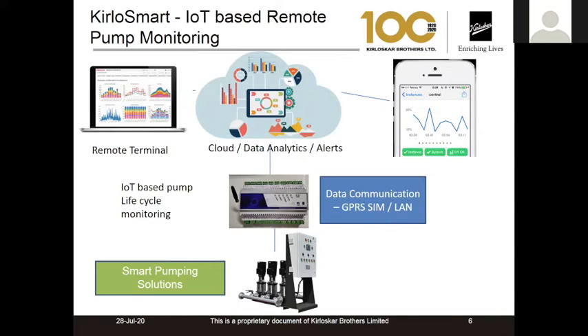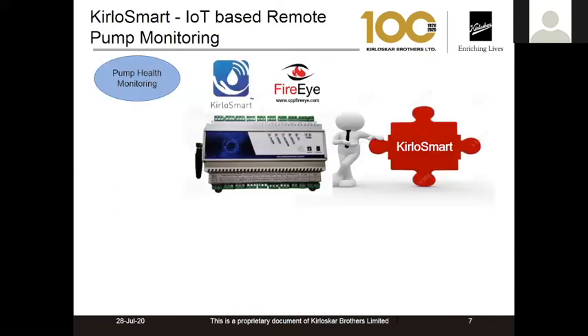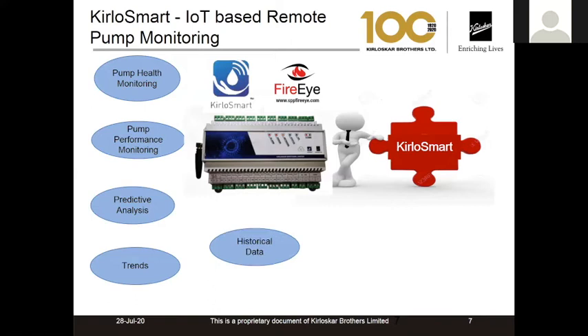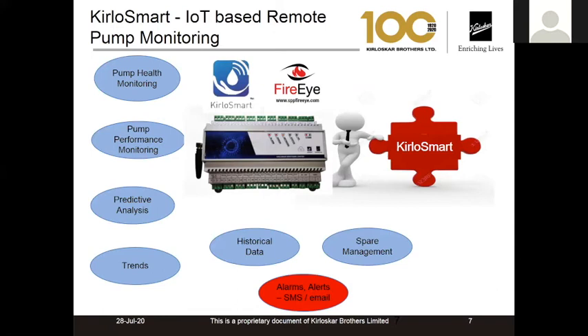So what this system will give customers is pump health monitoring, pump performance monitoring, predictive analysis, so early attention to issues or problems, trends, and historical data for analysis. Alarms and alerts can be communicated by SMS and emails. A spare management function is inbuilt, so whatever spares are about to expire, the system will intimate about them. It's a user friendly and easily configurable device. Customers can also get reports, like monthly or quarterly reports.